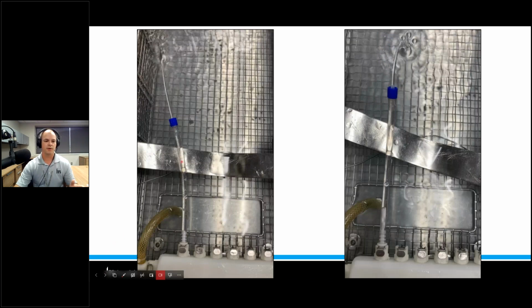Okay, so this one over here is a picture on the left of a Sonic that is in operation, and I made it shoot out of the water so you could actually see the stream, and hopefully you can tell, but there is a noticeable difference between the stream on the left here and the stream on the right. And so what I did was I used an accessory over here with a broken O-ring. All right, so that broken O-ring did impact the flow of that water through the channel and through the accessory port. So it is a very reasonable possibility that just a broken O-ring will impact and cause that failure, which is what we saw in that real life case study.